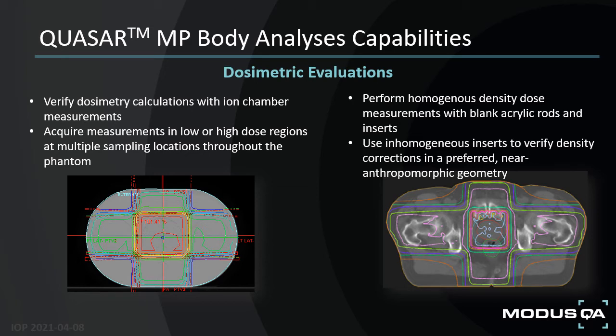This is actually particularly important not only to validate if the correct amount of treatment dose is being delivered to the target volume, but it can also simultaneously assess the dose distribution throughout the irradiated region, given that you have access to multiple ion chambers.